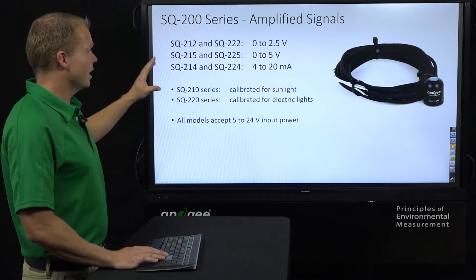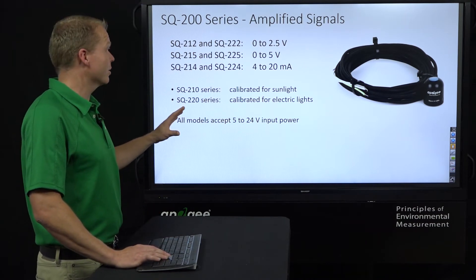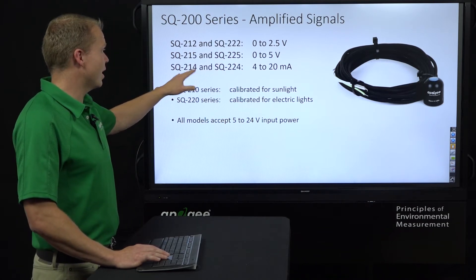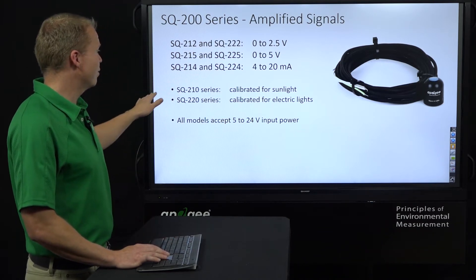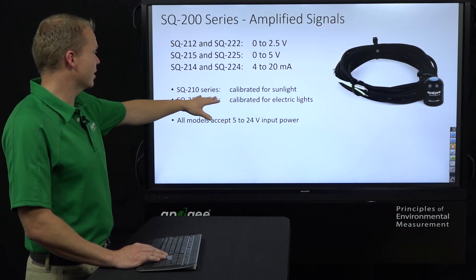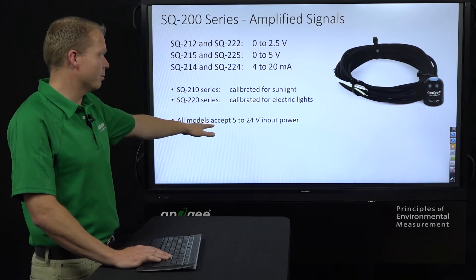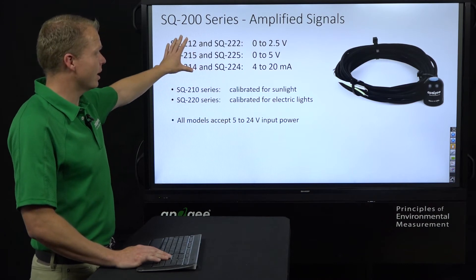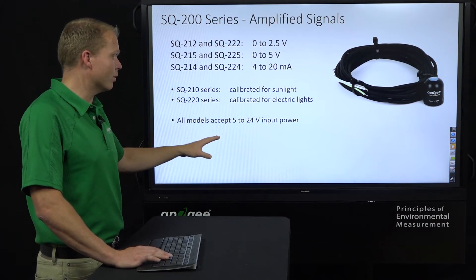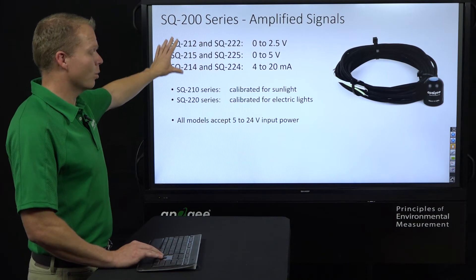The SQ200 series takes that same sensor and amplifies it into a voltage usable on your logger. The 212 and 222 output 0 to 2.5 volts; the 215 and 225 output 0 to 5 volts; and the 214 and 224 output 4 to 20 milliamps. The 210-series models are for sunlight, and the 220-series for electric lights. These all need to be powered — between 5 and 24 volts — and the sensor will automatically regulate and give the output accordingly.